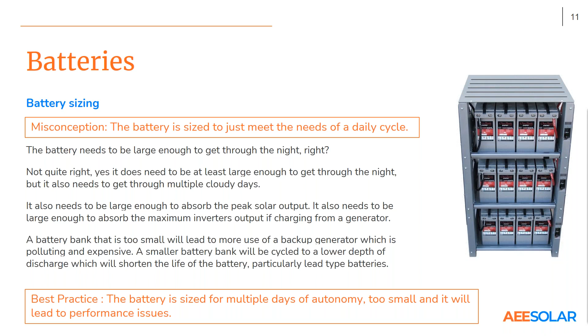So again, I think the thing that we have to coach people on is, we size the battery bank to multiple days of autonomy, ideally. Also taking into account how many charge amps and discharge amps you're going to have from the system. If you've got a small battery bank and you're dumping a ton of current into it, or pulling a ton of current out, it's not going to last very long, and you're not going to have good performance. So keep hammering that point home.